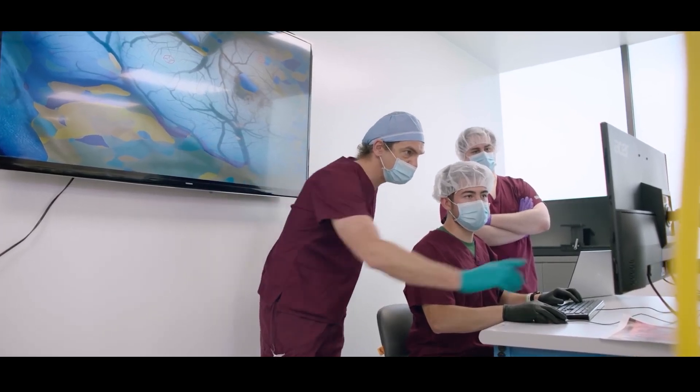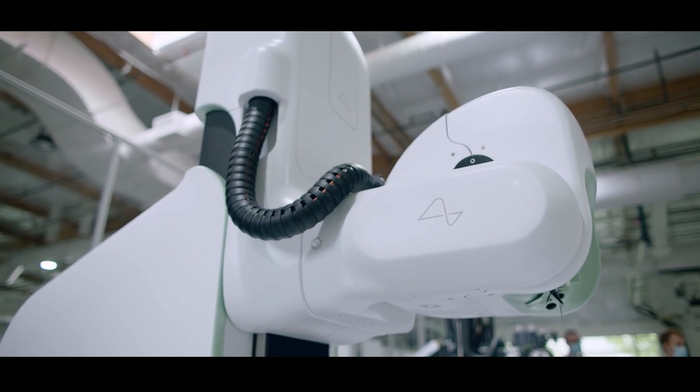They are mainly looking for moisture to get into the device. Designers are always keeping an eye on the implant's internal humidity. Over time, there will be a rise, but it will be very slight and gradual. Additionally, they want to monitor the batteries and the system's durability over time.